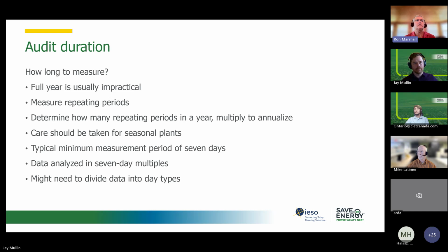But the typical minimum measurement in a regular shift oriented plant is about 7 days, and if it's longer than that, we would slice the data up into 7 day multiples. And sometimes you have to break the data into day types, right? If there are different processes running on Monday, Tuesday, Wednesday, and then Thursday, Friday are different, right? We have to segregate those days, add up the number of days of each day type to come out with a really good annualized baseline.